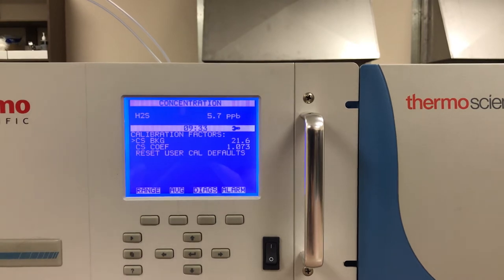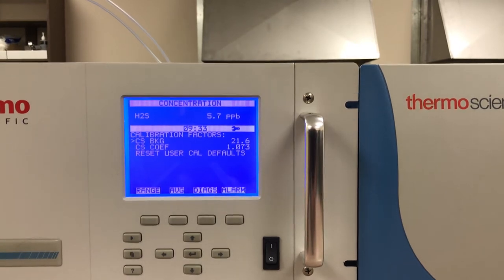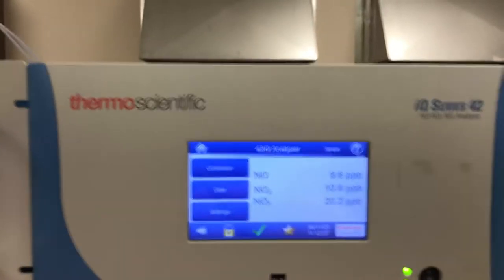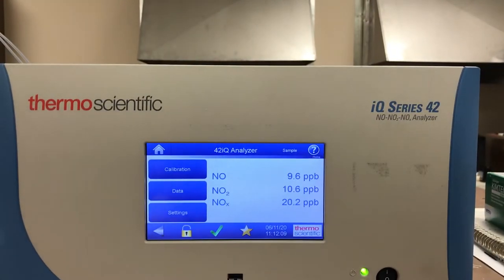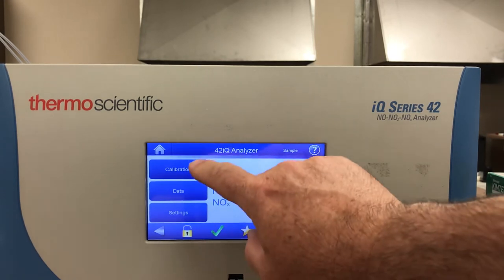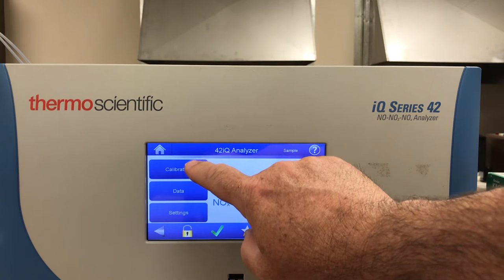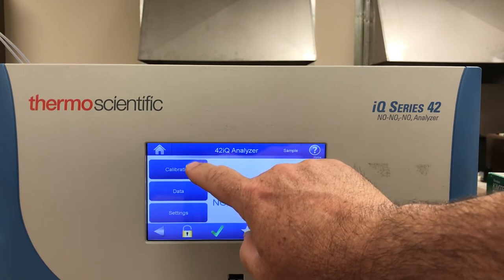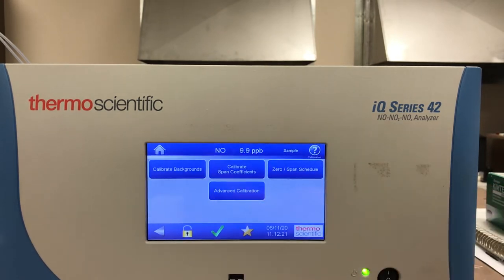Now if I was to do this on the i-Q series — this is the 42iQ NOX — there are no more manual push buttons and no software buttons. The top button on these i-Q series instruments is the calibration button. I push that and...